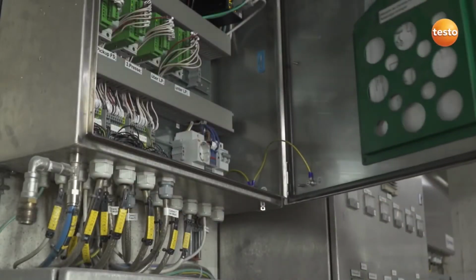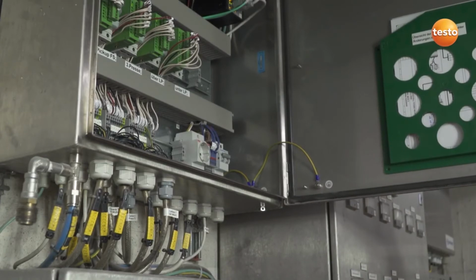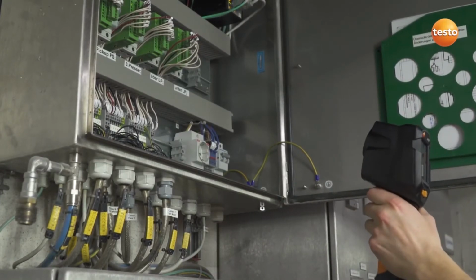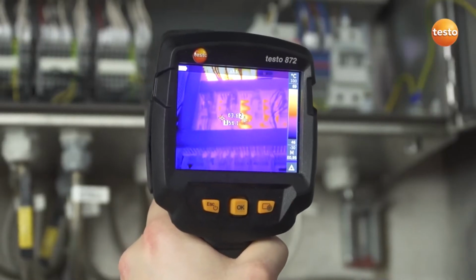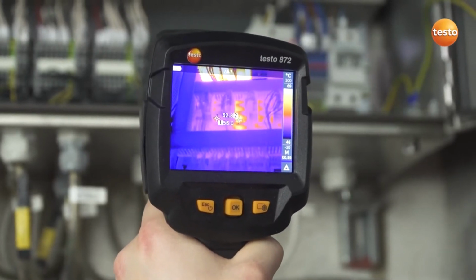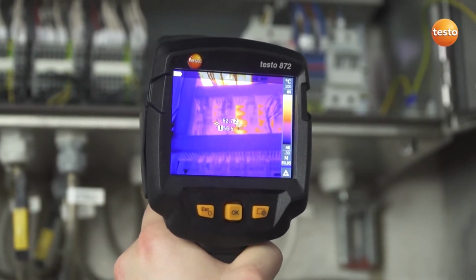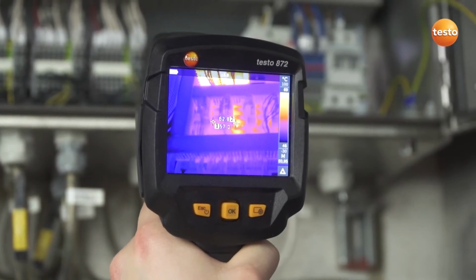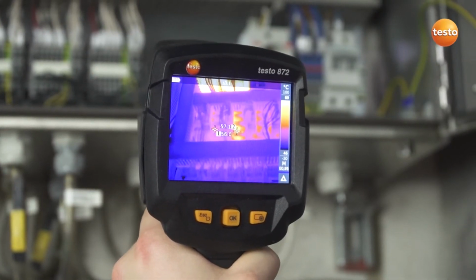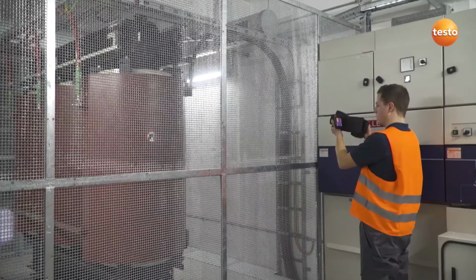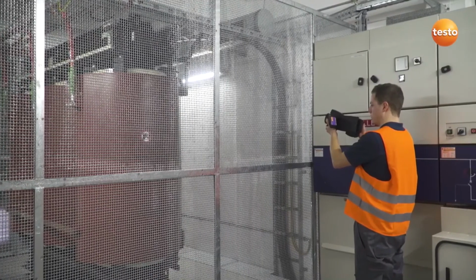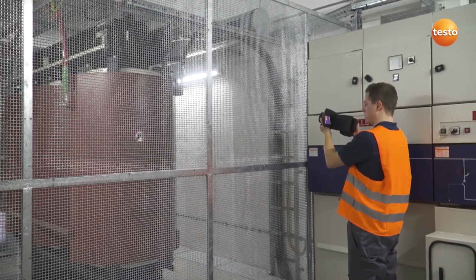The switching cabinets of machines can, of course, also be quickly tested with a Testo thermal imager. In these cases, the delta T function allows the temperature values from two freely selectable measurement points to be directly compared and the differential temperature read off. We then check the connections and insulation of this transformer.